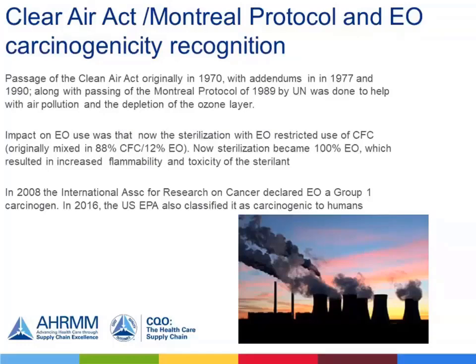That was followed by the Montreal Protocol, which was an international movement supported by the UN to do the same thing globally. So the impact was that after this happened, ethylene oxide was now going to become a single-use sterilant, so it was no longer mixed with the chlorofluorocarbons. So you had 100% ethylene oxide, and while that was better for the depletion of the ozone layer, that resulted in an increase in flammability and toxicity of the sterilant.